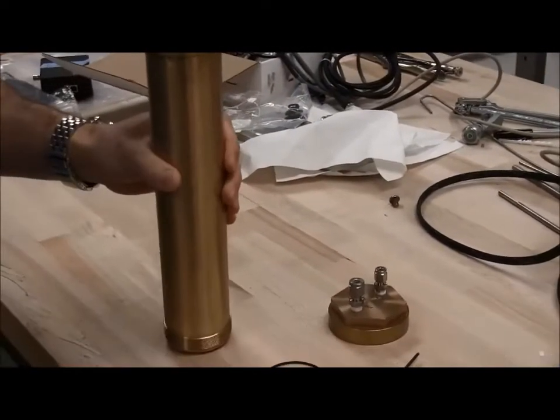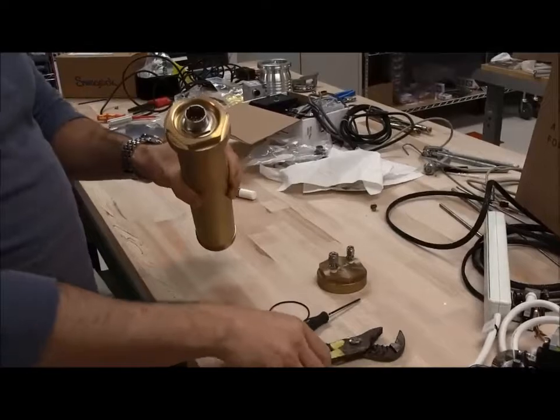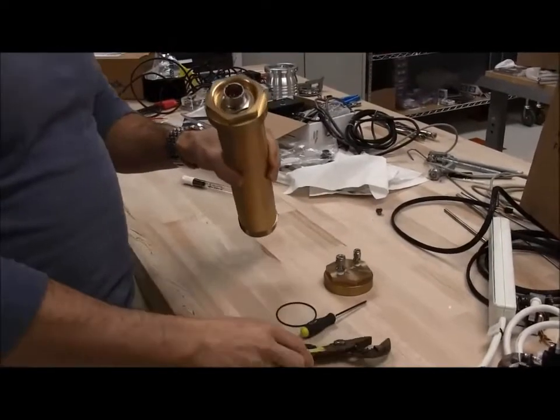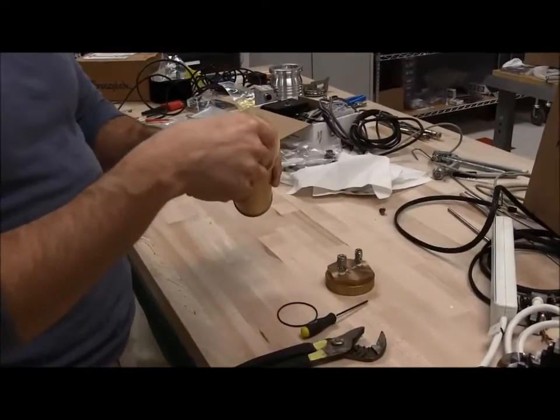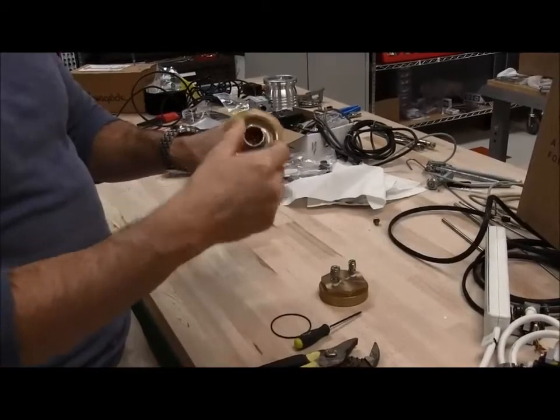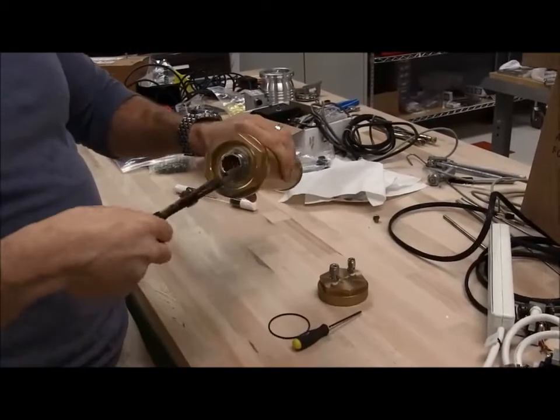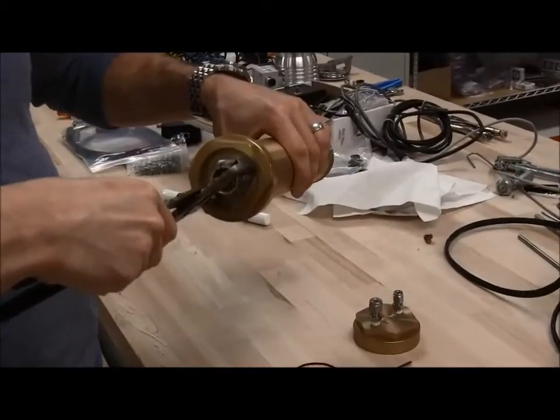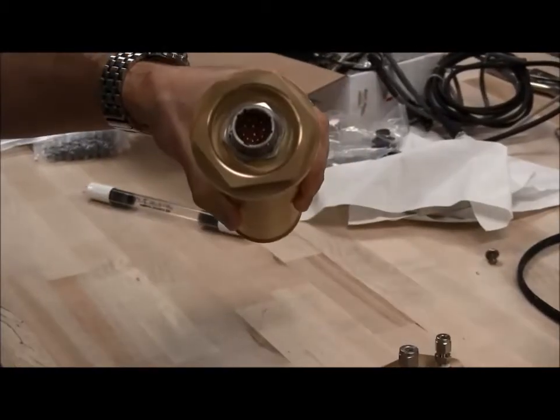Then to get access to the lamp itself, you need to go to the top connector here. If you have it, a 1 3/8 inch socket driver will remove this nut, otherwise a pair of channel locks that'll fit in there to just gently unscrew the nut.